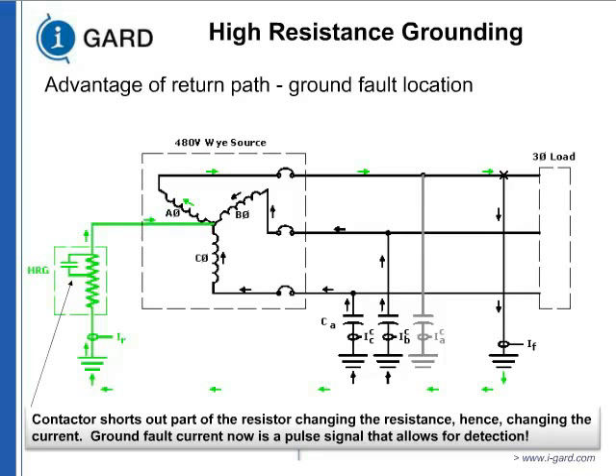What are some of the advantages of high-resistor grounding? First, if you recall, I told you the delta system has no ground return path. High-resistor grounding gave us a method to have a return path. So if you have a ground fault, you could locate it. How did the technology come about for locating? When I say we did that, don't take it to mean that I designed it. I'm just a practitioner. The technology was built because the current is so low, sometimes about 1 amp to 5 amps, normally closer to 1 to 2 amps, it was very hard to detect.